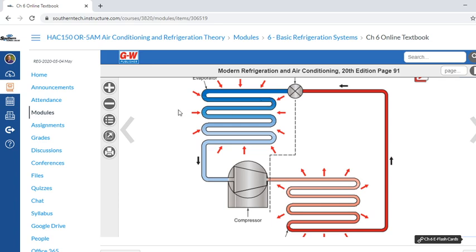In this picture, they have a dotted line running from the bottom of the compressor to the top of the metering device, which shows a division between the high side on the right and the low side on the left. And that's a very important spot, because to diagnose a unit, you have to know where the problem exists, either on the high side or the low side.